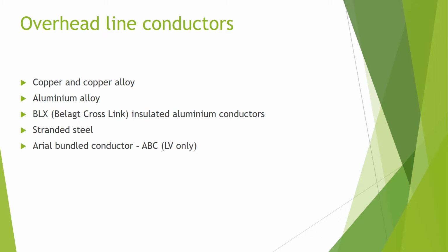Overhead line conductors. Overhead lines basically fall into 5 material groups: copper and copper alloy, aluminium alloy, BLX covered aluminium conductors, stranded steel, and aerial bundle conductor, also known as ABC.